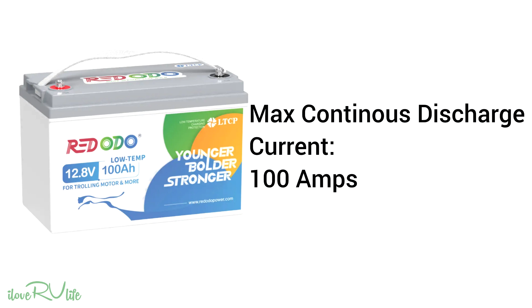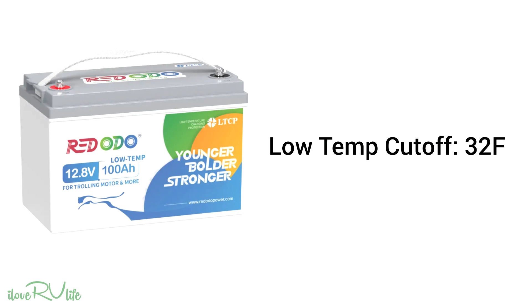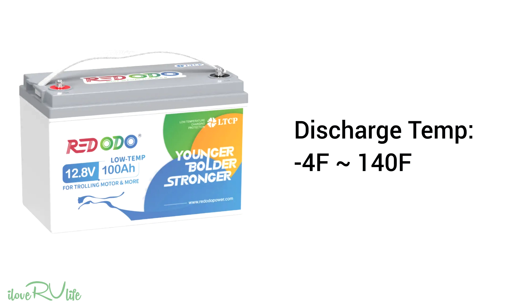You can have a continuous discharge of 1,280 watts, or a maximum continuous discharge current of 100 amps. Low temperature cutoff is 32 degrees Fahrenheit — you don't want to charge a lithium battery below that. Charge temperature range is 32 to 122 degrees Fahrenheit, discharge temperature range is -4 to 140 degrees Fahrenheit, and the recommended charge is 20 amps at 14.4 volts.